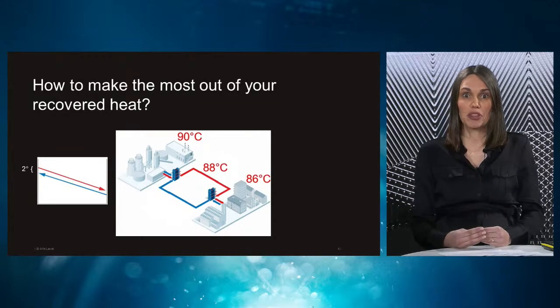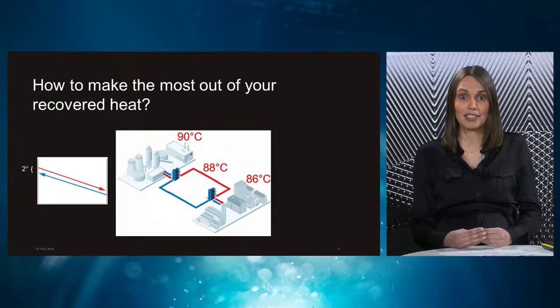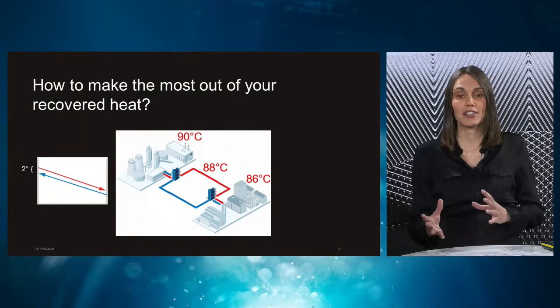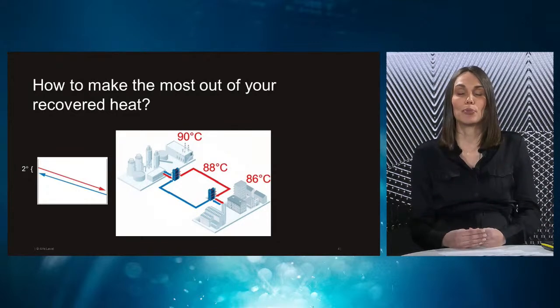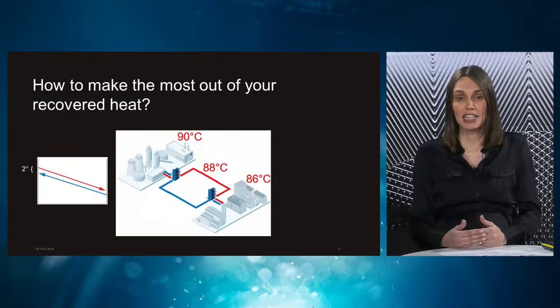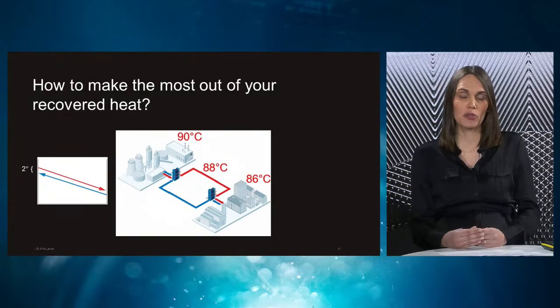In this example shown in the picture, we have an industry with waste heat available at 90 degrees, and the temperature approach is just 2 degrees Celsius. This industry exports heat via an intermediate loop, and it's quite common to have an intermediate loop to connect the use and the supply of heat, both to ensure interdependence and to cover the distances between the two sites. And here it's exported to a district heating network, for example. And by having just these 2 degrees temperature approach, we ensure that we keep as high temperature as possible available for reuse.